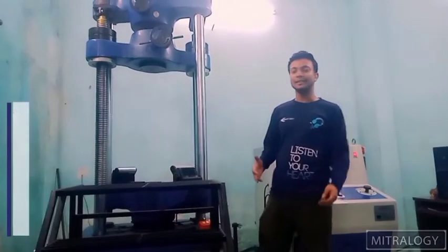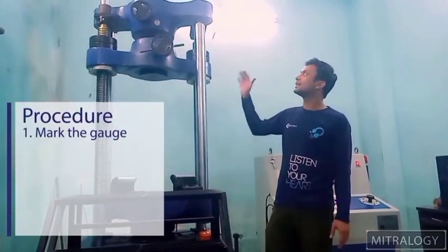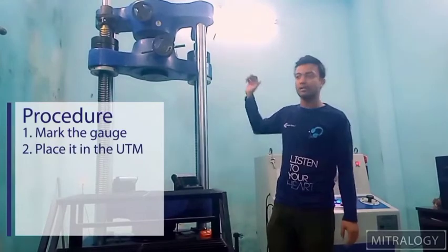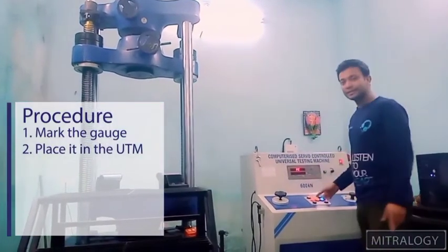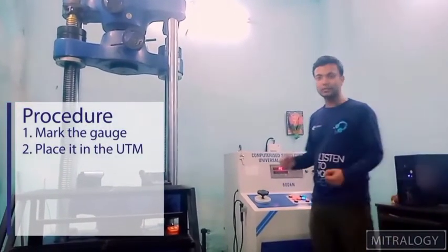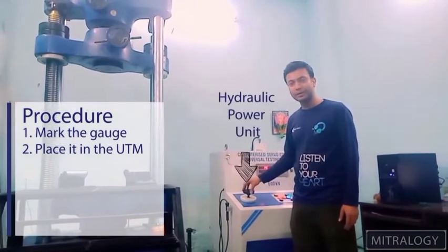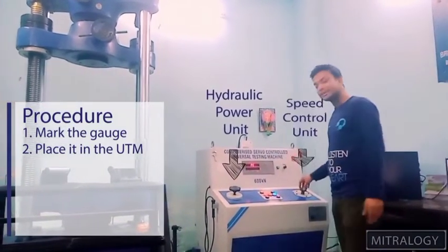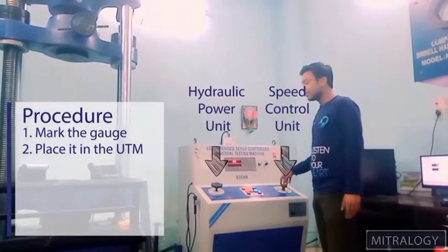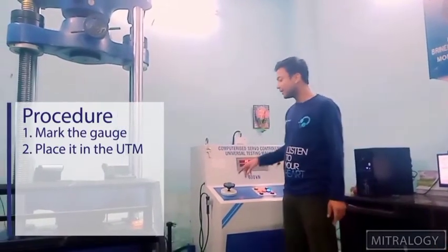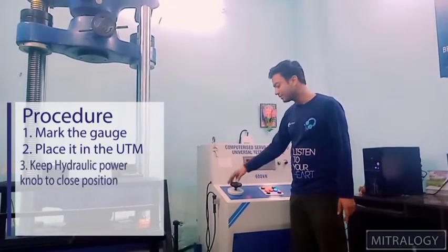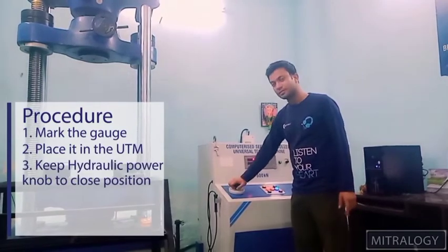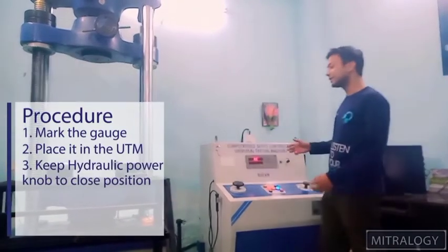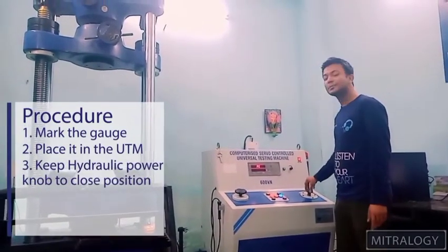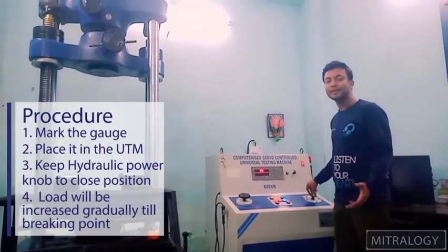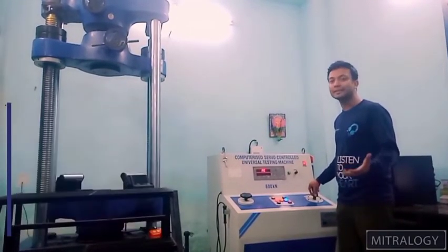As you can see, we put the sample in the UTM and there is a control unit. There are two main components in the control unit. One is the hydraulic power unit and one is the speed control unit. Before starting the test, we have to close the hydraulic power unit. And after starting the test, we will increase the power gradually depending on how much speed we need.